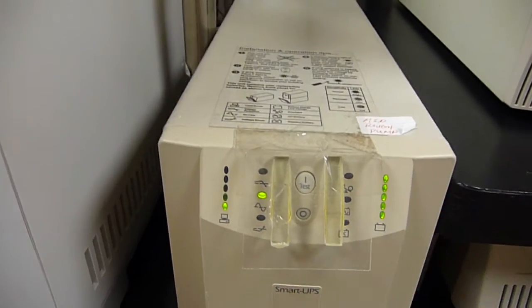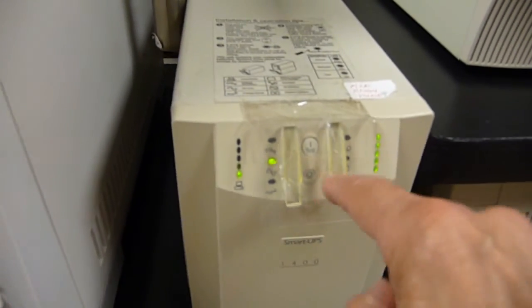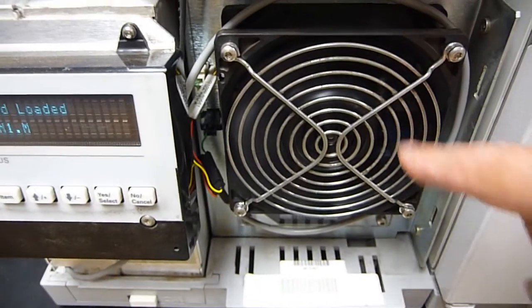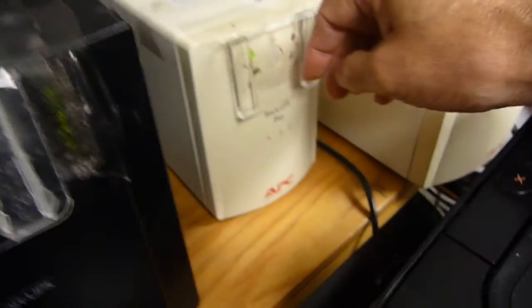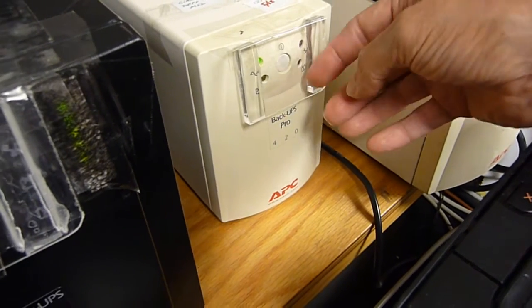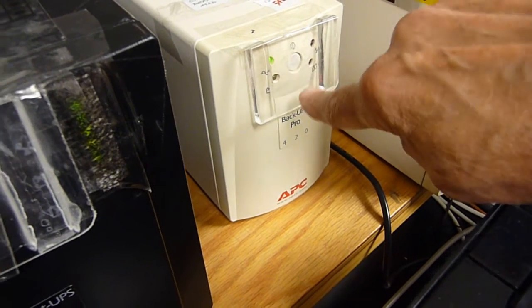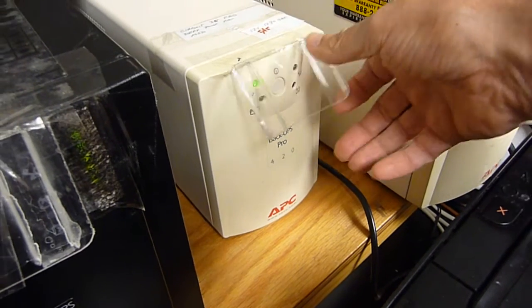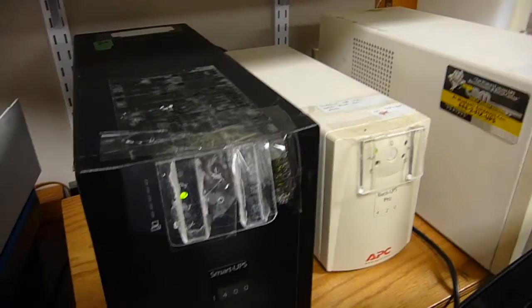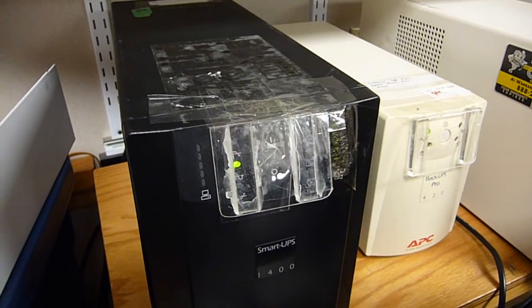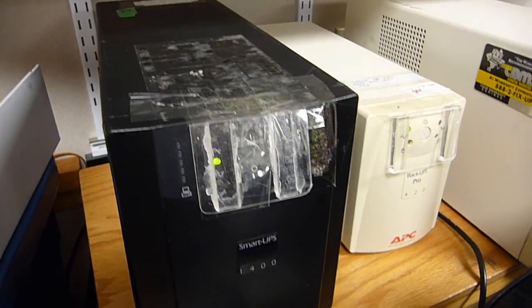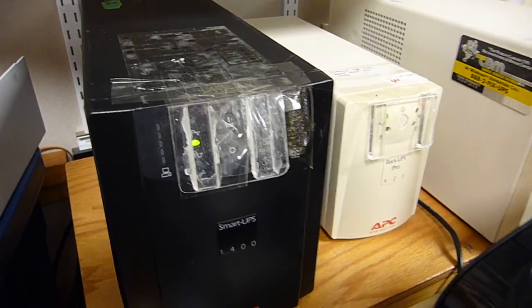And this way, you can still see the indicators. So for the rough pump, it's important to have some sort of switch protection. And naturally, for this diffusion pump fan, same sort of thing. And a little plexiglass. You cannot turn it off unless you remove the protection. Something I would highly, highly recommend if you go down the road of using UPSs in order to maintain instrument uptime.